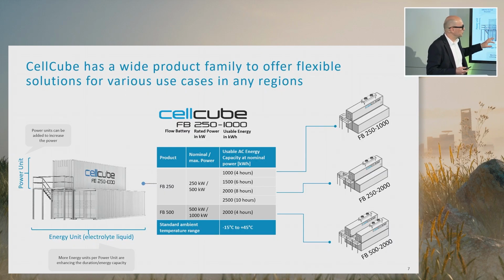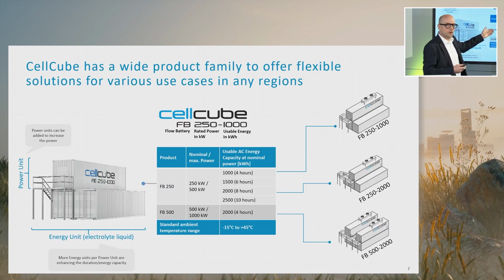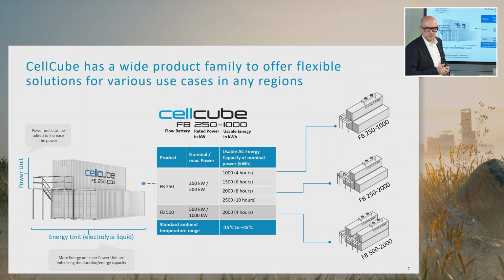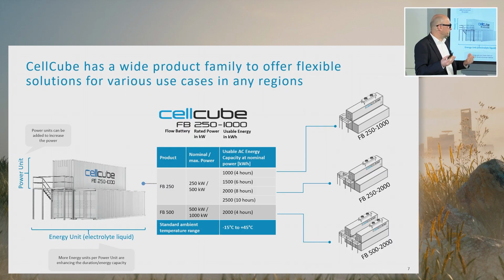With these modules, we can combine different models of our flow battery. For example, if you have one top container, it's the FB250. It has a nominal power of 250 kilowatts. And every CellCube can have 200% of maximum power, so that would be 500 kilowatts.